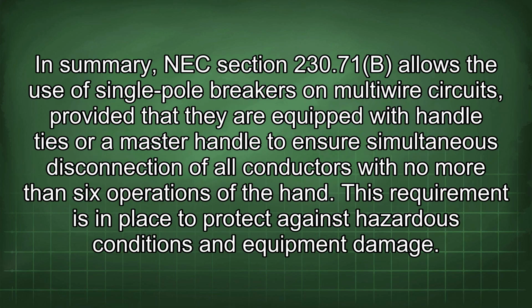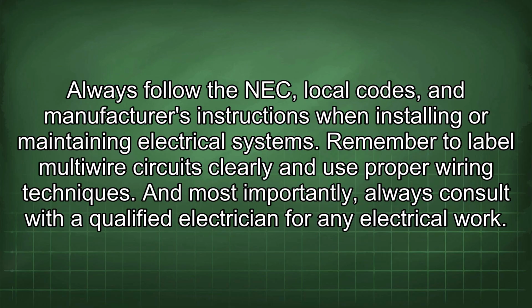In summary, NEC Section 230.71(B) allows the use of single-pole breakers on multi-wire circuits, provided that they are equipped with handle ties or a master handle to ensure simultaneous disconnection of all conductors with no more than six operations of the hand. This requirement is in place to protect against hazardous conditions and equipment damage. Always follow the NEC, local codes, and manufacturer's instructions when installing or maintaining electrical systems.